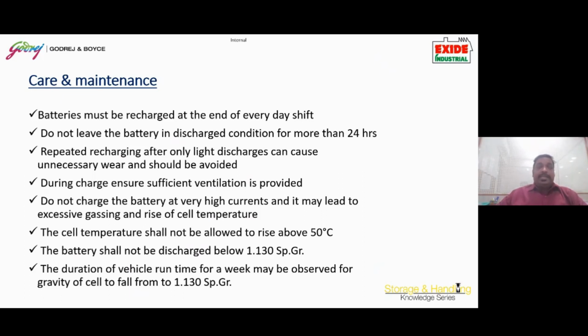The charging room should be designed with sufficient ventilation, because you are charging up to 2.65 volts, and at 2.40 volts there is hydrogen evolution from the battery. Hydrogen is a very highly inflammable gas. It should not be allowed to accumulate inside the room. Hence, the charging room should be sufficiently ventilated and sufficient airflow should be there. It should not be a closed AC environment.